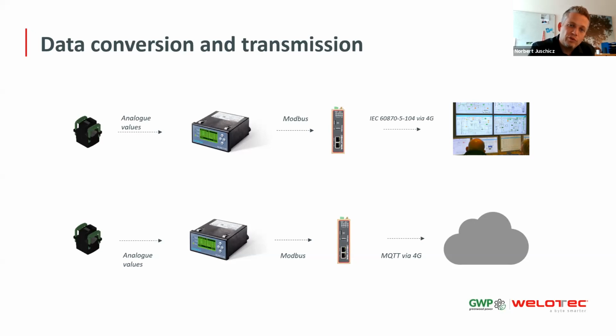a feeder condition monitor, which is able also to detect earth fault directions in isolated, compensated, or low impedance star point grids. And this device can also provide, for sure, the standard power factors, the actual voltage level and current levels. And with our sensors, this is a package which is closed, and from the FCM, you can make the next step into the chain via Modbus. But now Jos will continue to present this solution.